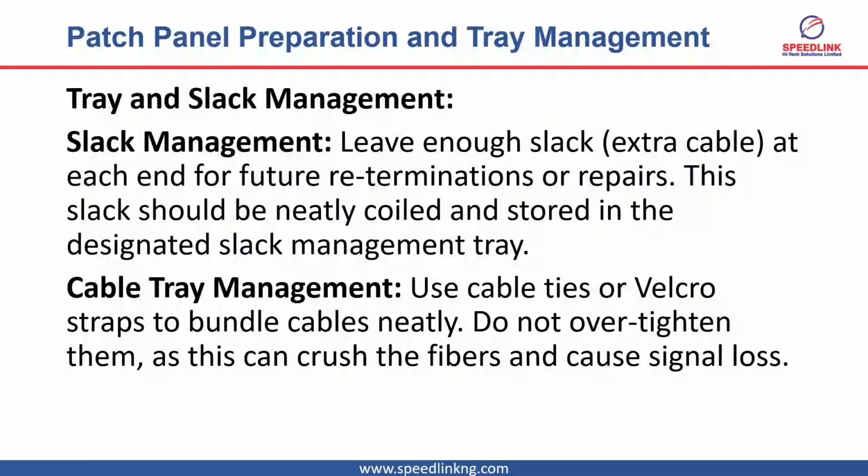For cable tray management, use cable ties. Cable ties, or we call them tie wrap, right? Or zip ties, or Velcro straps to bundle cables neatly. So do not over tighten them as you are zip tying a cable. Don't go and tighten it too much. Remember, you are pressing a fiber optic cable. If you tighten it too much, it will cause micro bend, isn't it? Do not over tighten them, as this can crush the fiber cables and cause signal loss. I hope you are following.